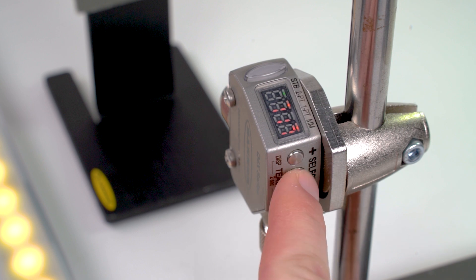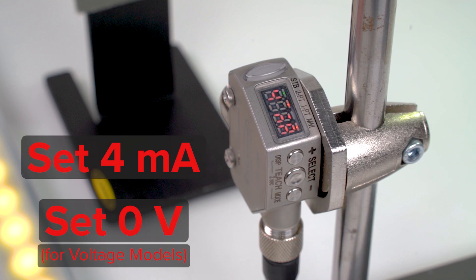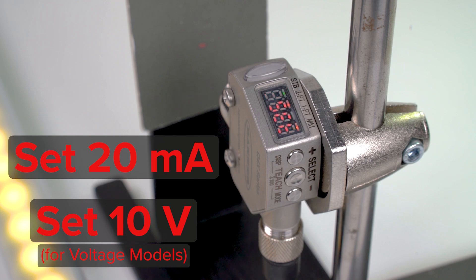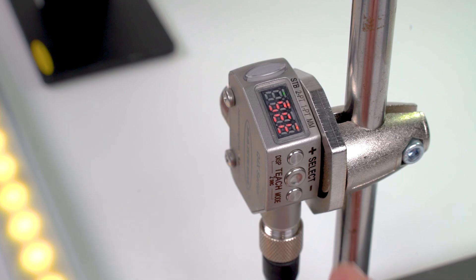To begin the teach process, press and hold the select or teach button for two or more seconds. The display will show set four milliamps. Present the target distance that will pertain to this end of the analog signal and press the select button. The display will then show set 20 milliamps. Present the target distance for this end of the signal and press the select button again.